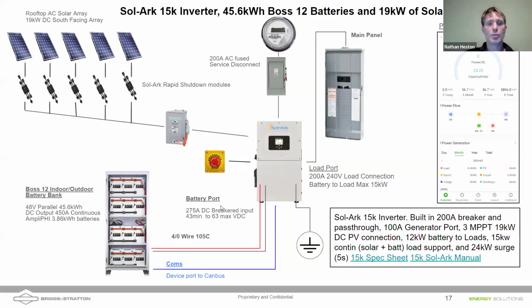Again, it has the ability to bring in large amounts of solar, both DC coupled and AC coupled solar at the same time. So if you're doing a retrofit, it's got AC coupled solar, maybe you've got 10 kilowatts on the roof, you want to supplement that with DC coupled solar, you can do so. And the AC coupled solar does not influence the amount of DC that you can bring in. You can still bring in an additional 19K.